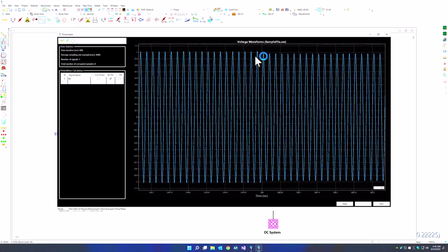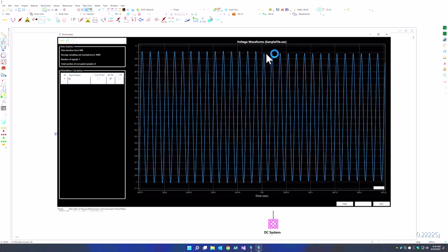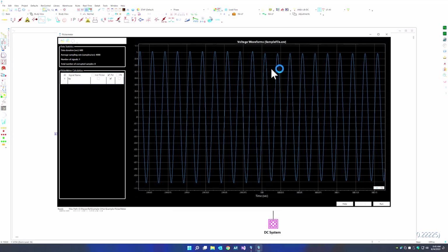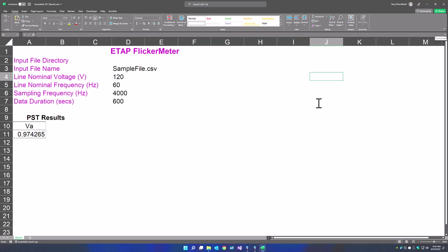You can see in the magnitude in the envelope here, there's a slight variation in voltage, and this is the whole purpose of the flicker meter, is to look at all these variations in magnitude in the given waveform and compute or calculate the short-term and long-term flicker index. Let's go ahead and compute the short-term index and see our result. Once the calculation finishes, you can see a simple Excel output that shows us the file name, the nominal voltage, frequency, and the sampling frequency, and how long was that data file.